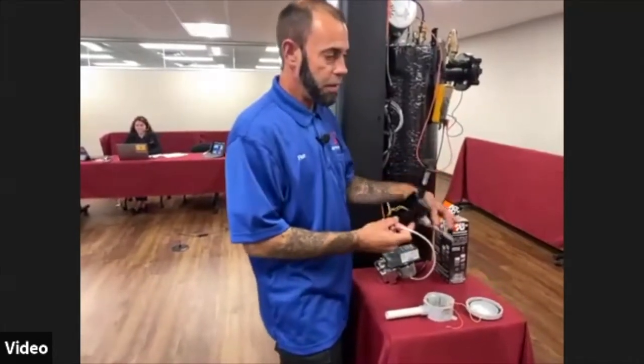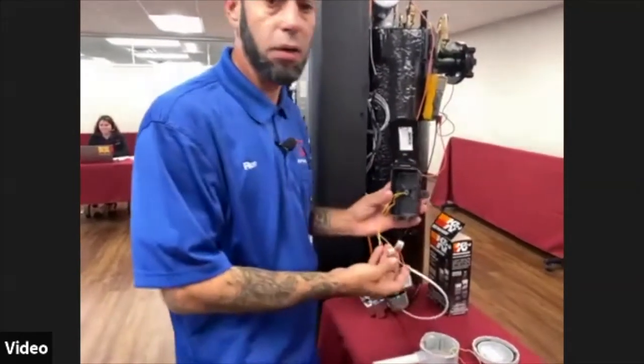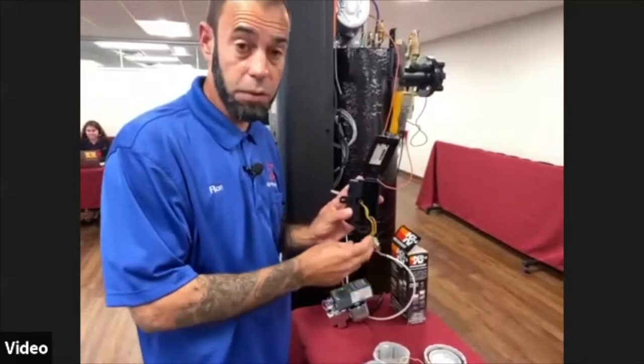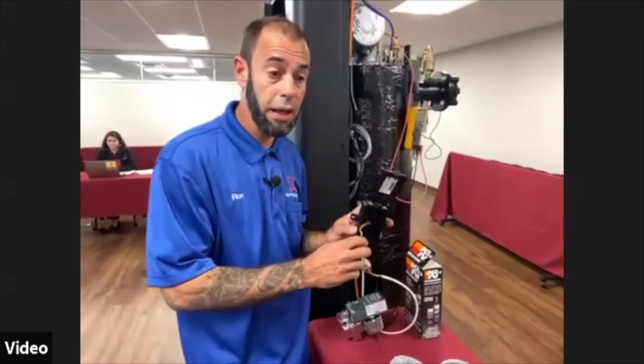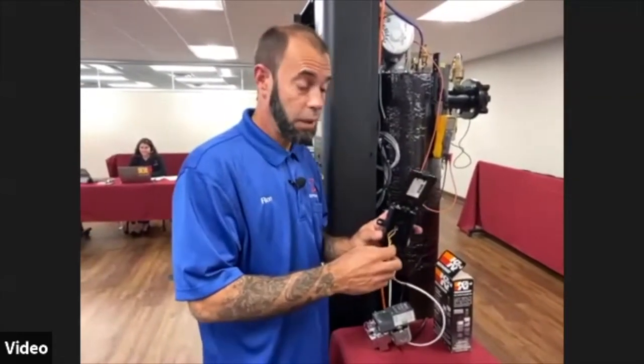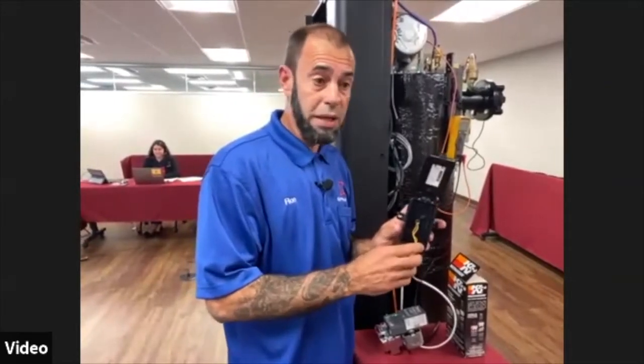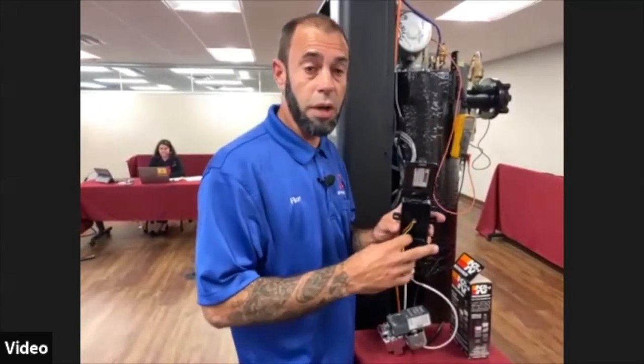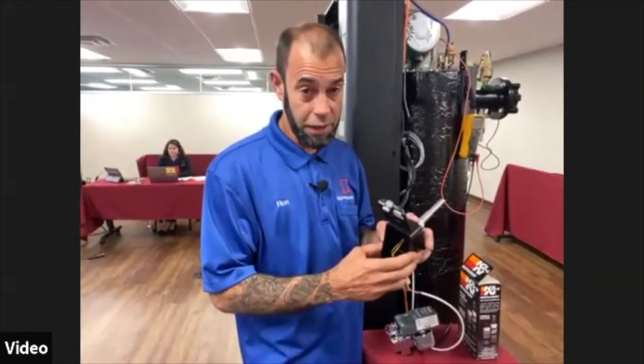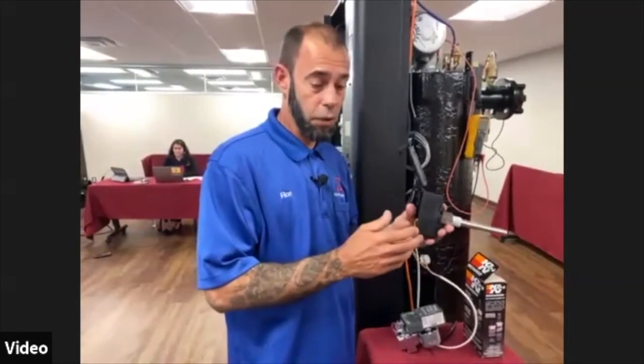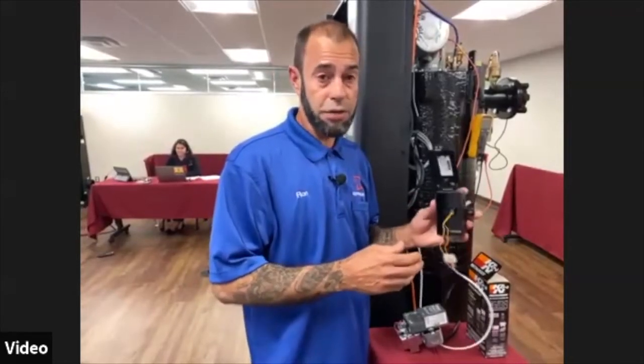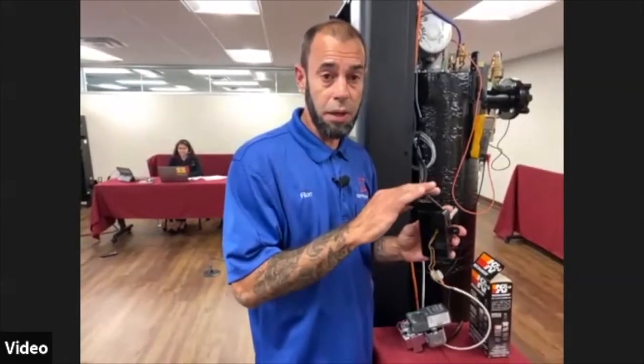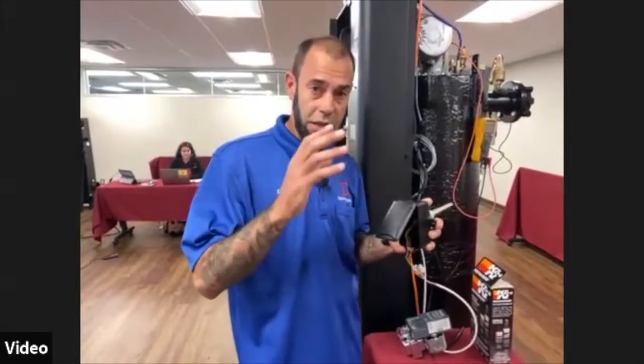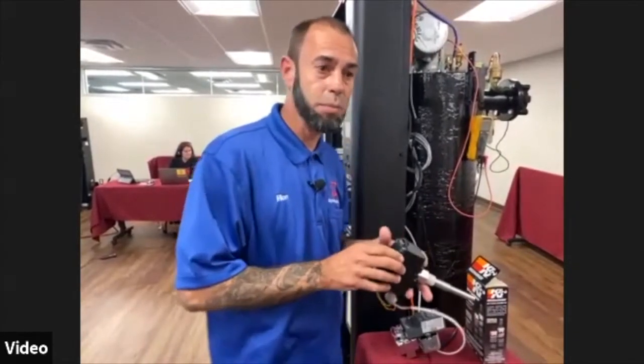So this would typically be mounted depending on what you're running. If you're running a variable primary, or if you're running a primary secondary. If you're running a primary secondary, it would be downstream of the last boiler after your closely spaced tees in the main header, supply header. If you're running a variable primary, it's still going to be downstream in the main header of the boiler, last boiler.